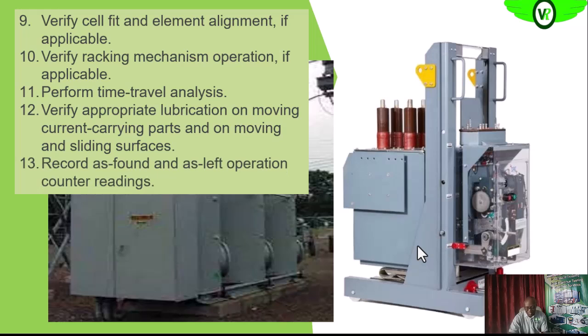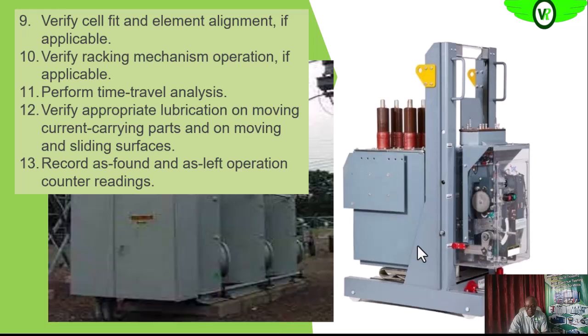After that, we can do our recording as to what we discovered and saw there, that is recorded as found. Then if there were any corrections made in the course of our inspection, because we saw some defects that needed to be corrected, after the correction we need to record that as left.